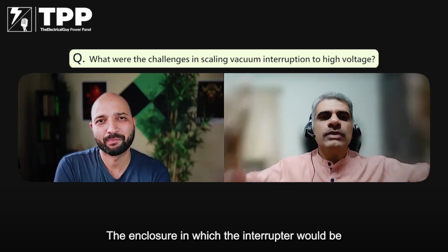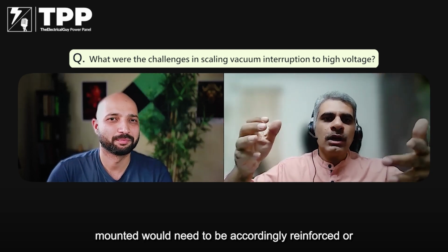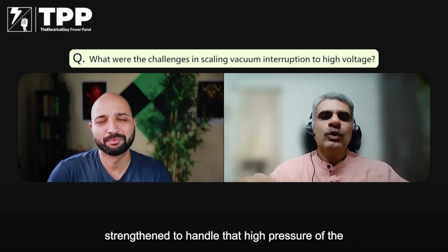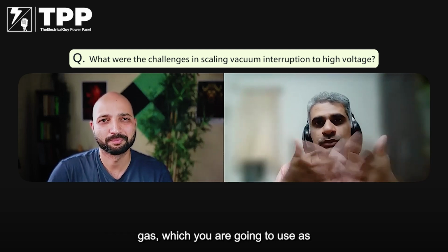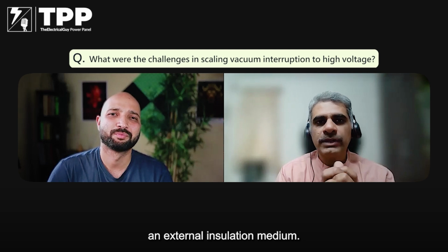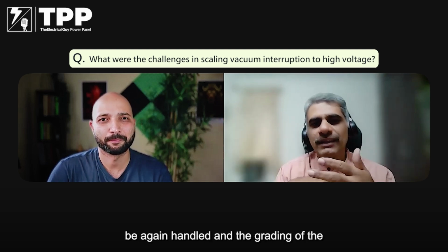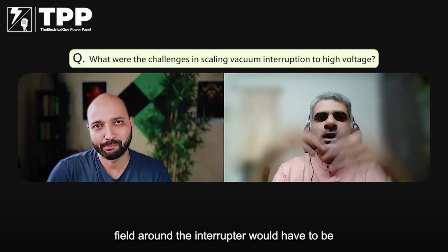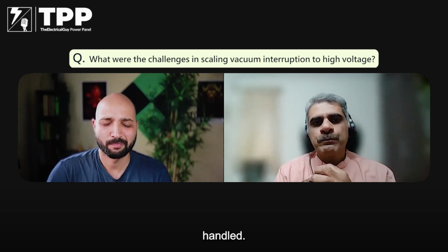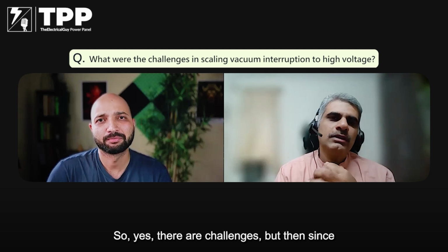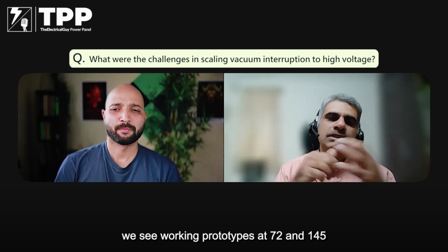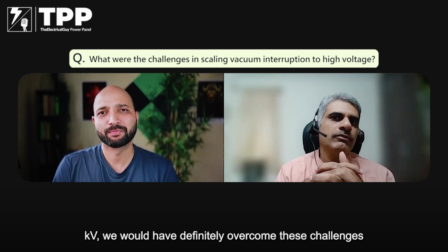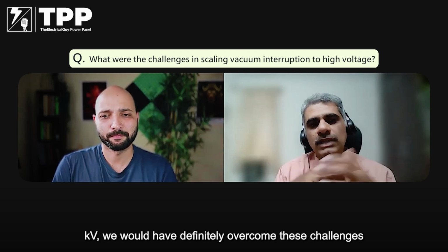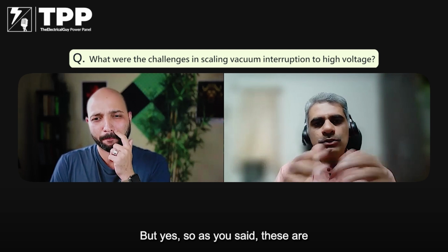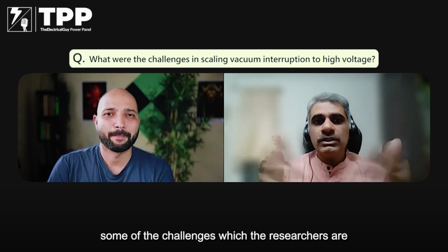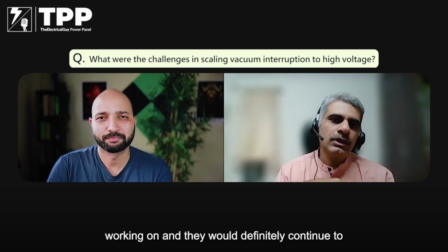The enclosure in which the interrupter would be mounted would need to be accordingly reinforced or strengthened to handle that high pressure of the gas which you are going to use as an external insulation medium. Then the leakage of that gas has to be again handled. The grading of the field around the interrupter would have to be handled. So yes, there are challenges, but since we see working prototypes at 72 and 145 kV, we would have definitely overcome these challenges to a certain extent. But yes, as you said, these are some of the challenges which the researchers are working on, and they would definitely continue to work on.